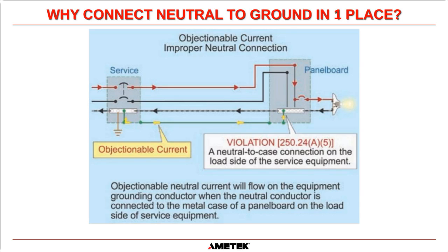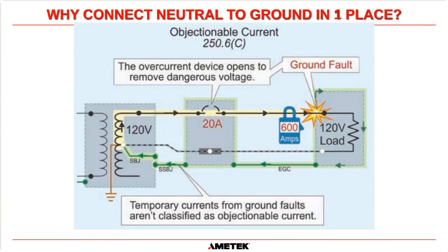So what you can see here is the neutral is connected to ground here. And what they're saying is if neutral is connected to ground here, then you are going to get objectionable current in the ground conductor, okay? Because what you want to happen is you want to have your neutral connected to ground here, and then if you do have a fault, then the fault current flows through the ground conductor, and that's the only time current should flow through the ground conductor, is if there's a fault, and then that will allow the supply, the MCC that supplies this transformer, to trip very, very quickly and prevent this fault from causing a fire. That's what the return ground path is trying to do. It's trying to make sure that a fault is cleared very, very quickly.